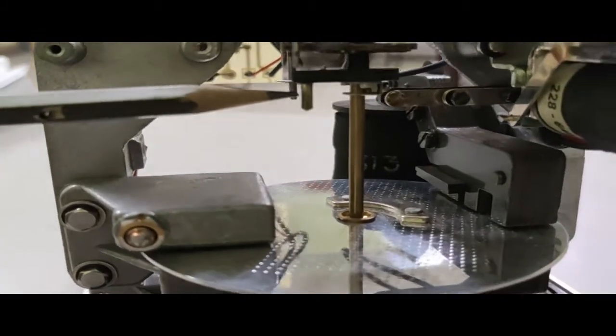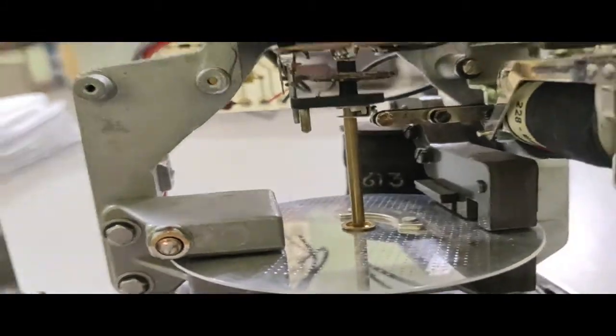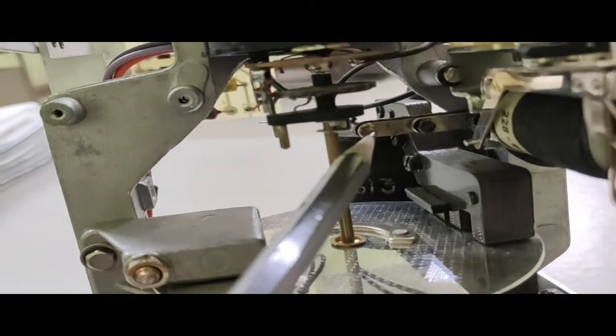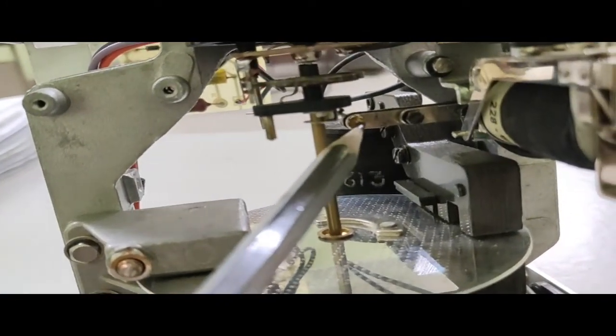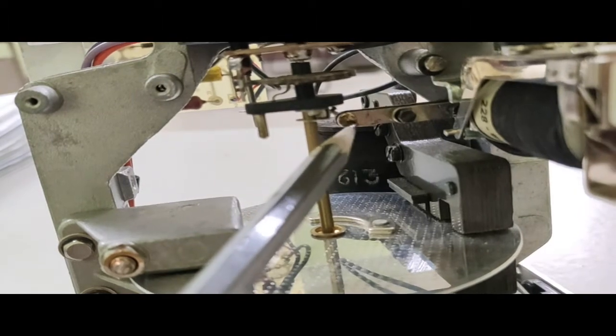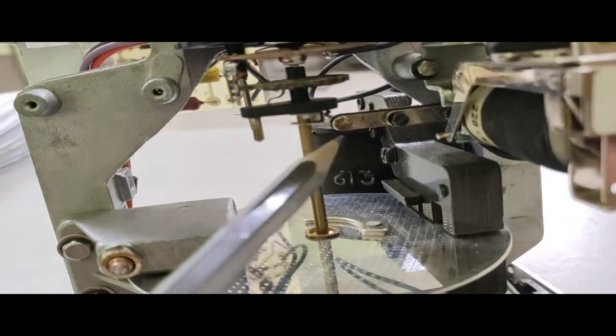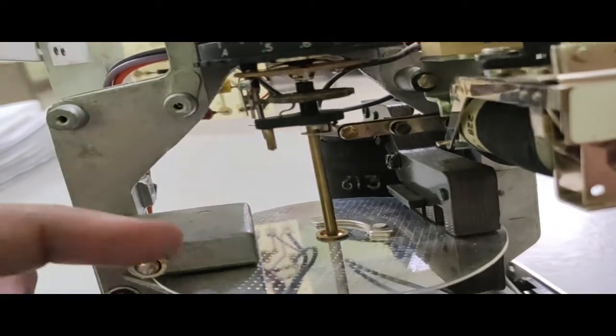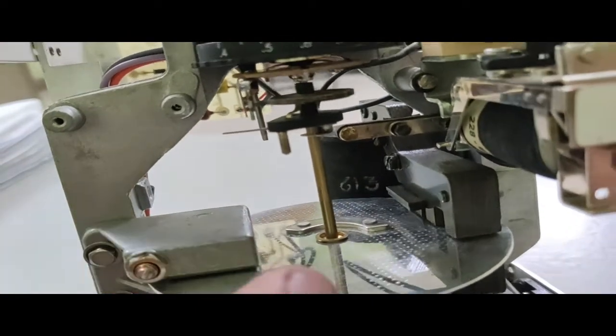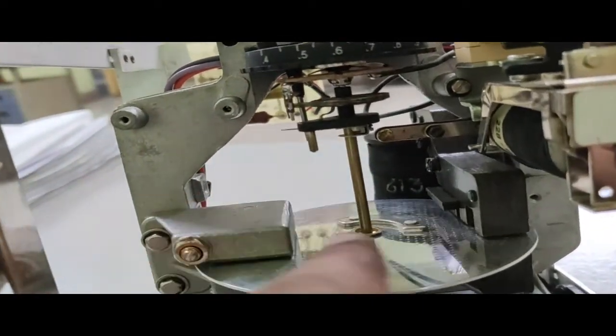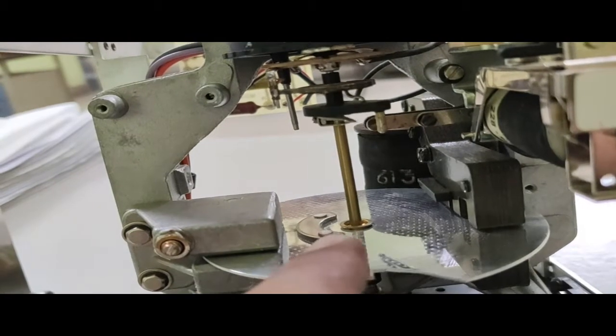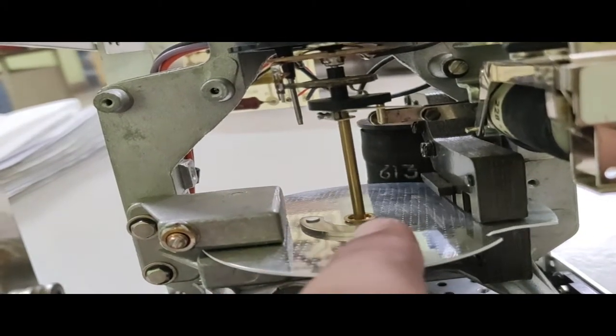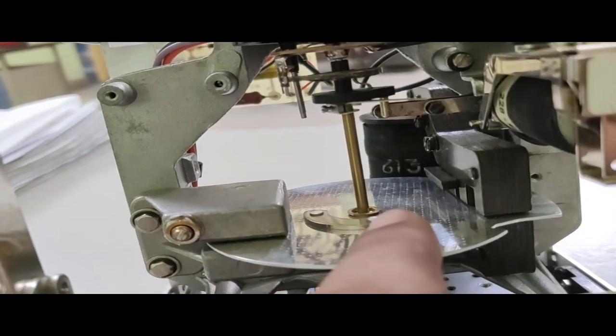Now what is this one? Here you see, this is the portion which is connected to the tripping circuit of the relay. Now this one is normally open. You see, this is normally open. When the disc starts rotating, along with the disc this one also rotates, and ultimately this creates some pressure on this normally open contact, and it becomes closed.